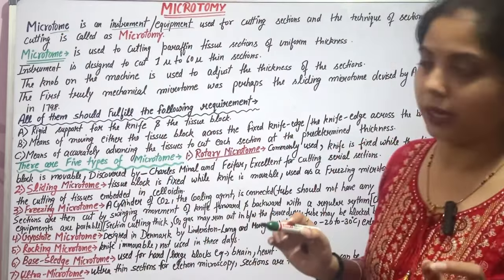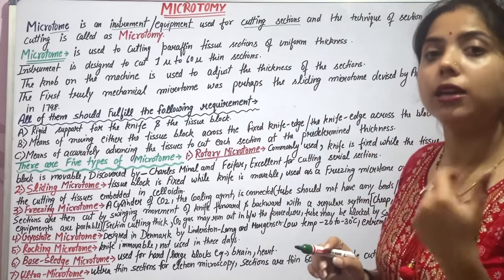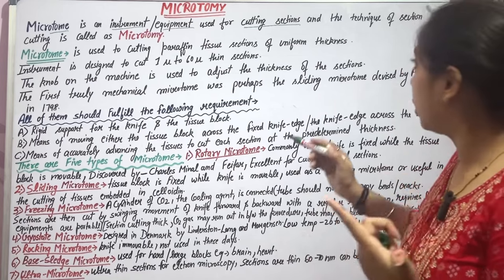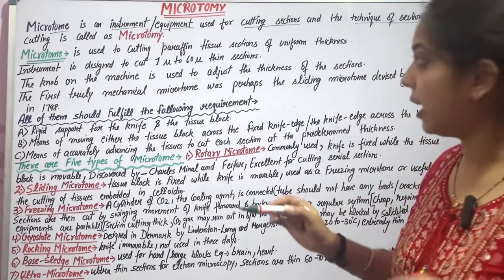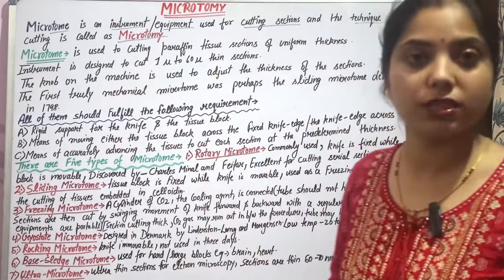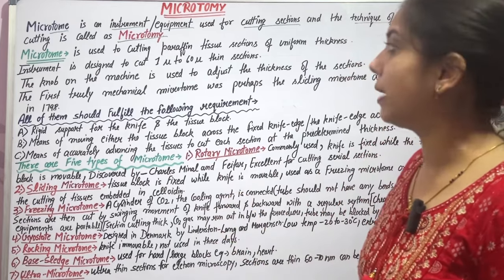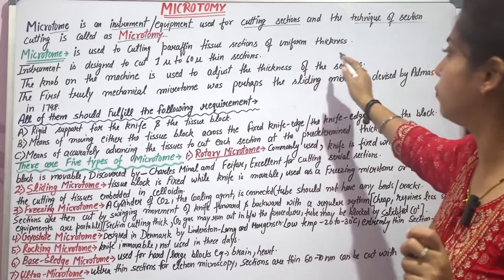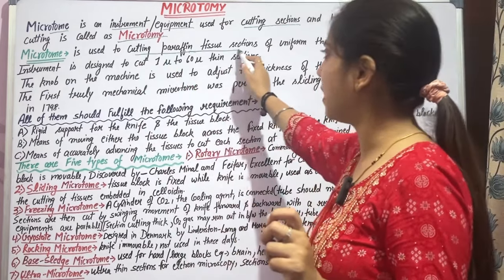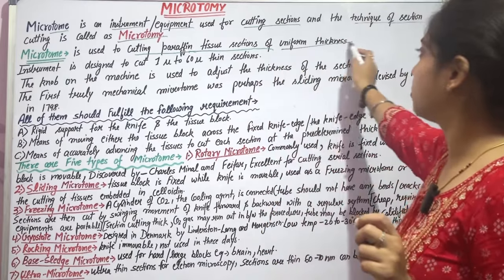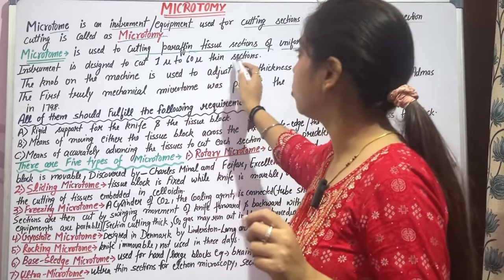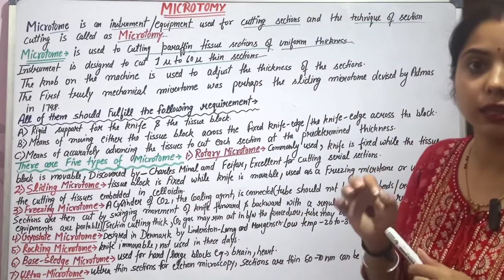The Microtome is an instrument used for cutting paraffin tissue sections of uniform thickness. The microtome is designed to cut sections from 1 micron to 60 microns in thickness. The thickness is adjustable to cut sections as required.